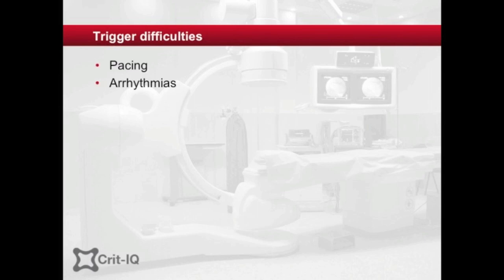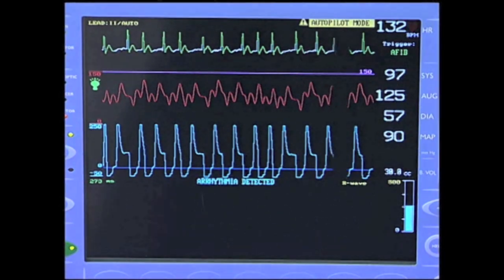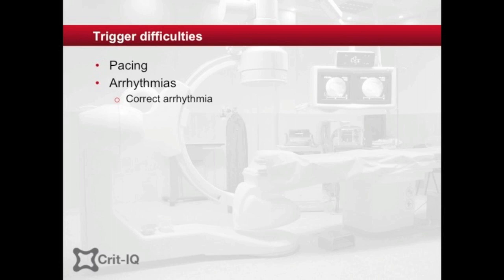Errors in triggering may occur with pacing or arrhythmias. In practice it is possible to support a paced patient with counterpulsation, but the trigger may need to change depending on the rhythm, the type of pacemaker — atrial or ventricular — and the patient's response to both therapies. Intra-aortic balloon pumps may find it more difficult to cope with irregular rhythms, for example ectopics or atrial fibrillation. The best way to overcome this is to attempt to restore a regular rhythm via electrolyte correction, cardioversion, or anti-arrhythmic medication. If the irregular rhythm persists, a trigger known as AFib can be utilized to deflate the balloon to match each R-wave as it occurs in real time — known as R-wave or real-time deflation.